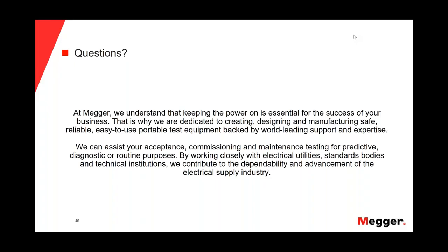For instance, if somebody bent too much the cable and crushed the jacket and inflicted mechanical damage to the insulation of the cable, then we will detect that problem, but because we have a mechanical damage in the insulation of the cable. But after the question, I will say no. With the partial discharge, we cannot detect issues in the shield or the jacket of the cable. We need to do the sheath test to find that kind of issues.